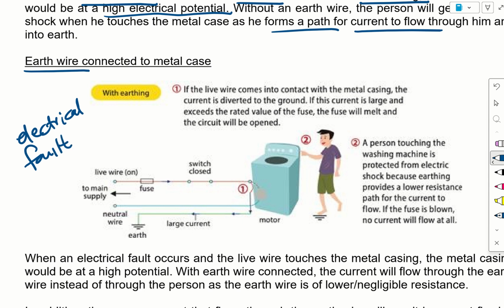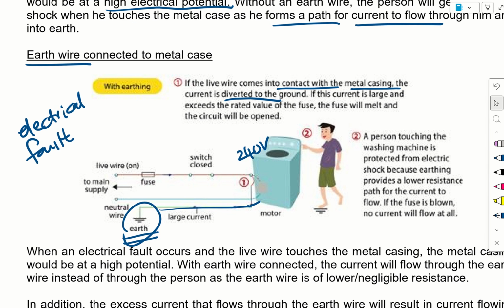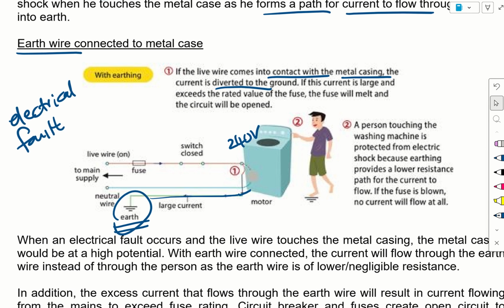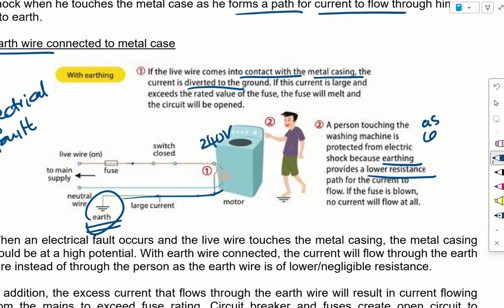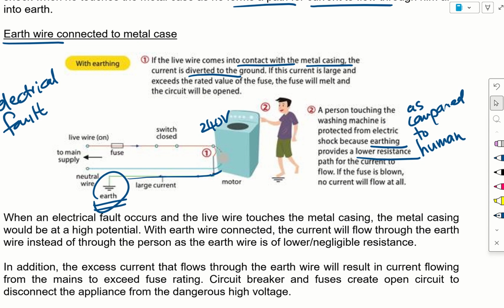Due to an electrical fault, the live wire comes into contact with the metal casing, so the casing is at high potential. But now, because there is an earth wire connected, the current will actually flow through the earth wire into earth instead. The person touching the metal casing will be protected from electric shock because the earthing provides a much lower resistance path compared to the human body, so most of the current flows through the earth wire.